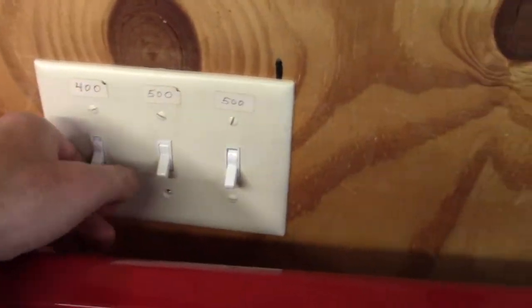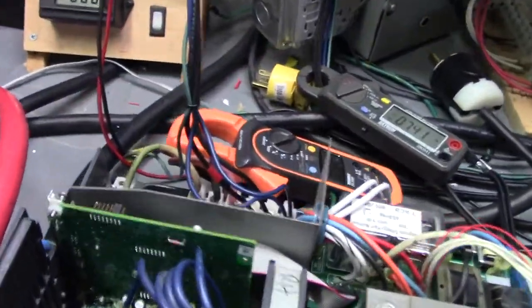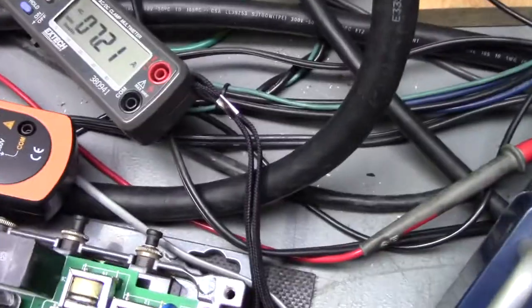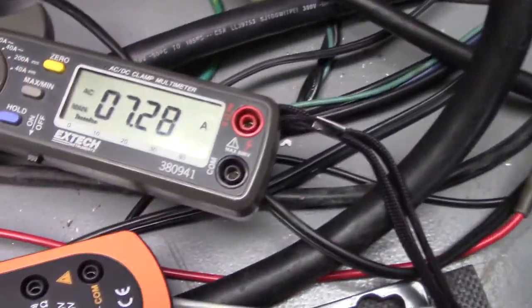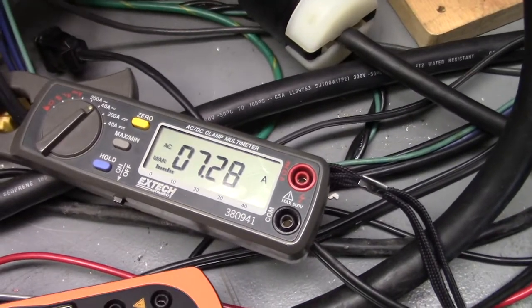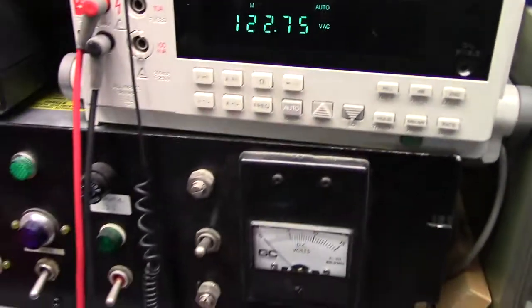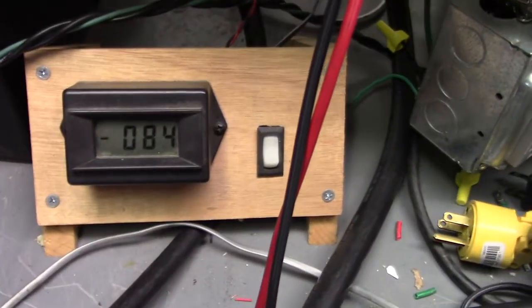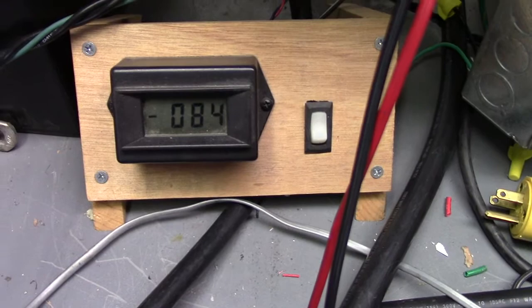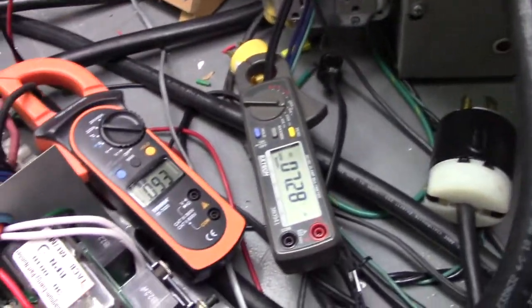About 1,000 watts of load. Now with 1,000 watts of load, I've got about 7.28 amps going out AC. We have 122 volts, and we have 84 amps coming out of our batteries. So that's in invert mode.